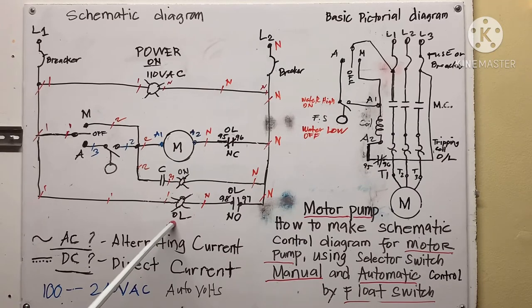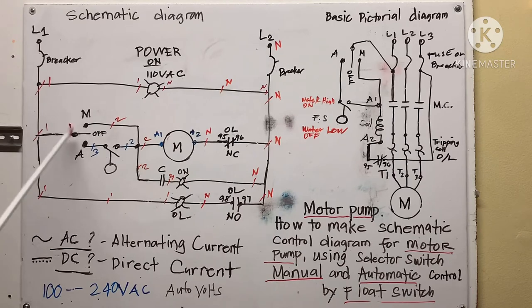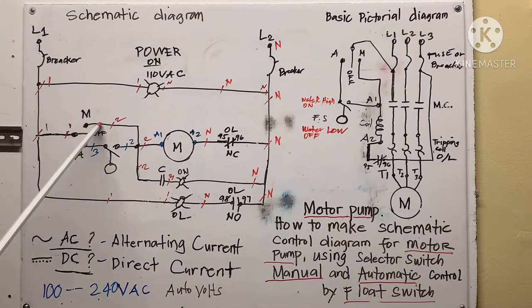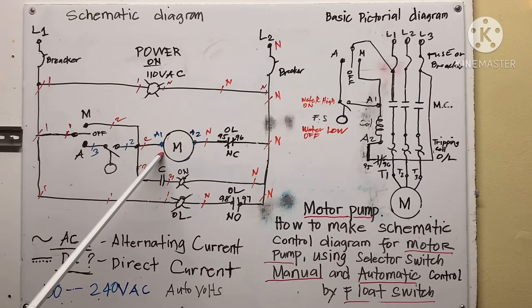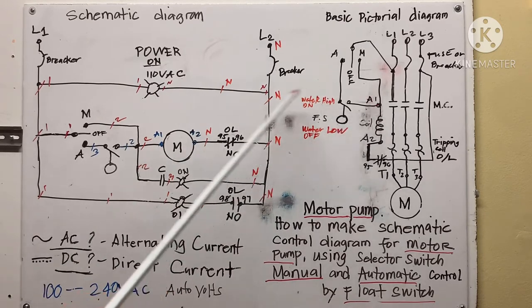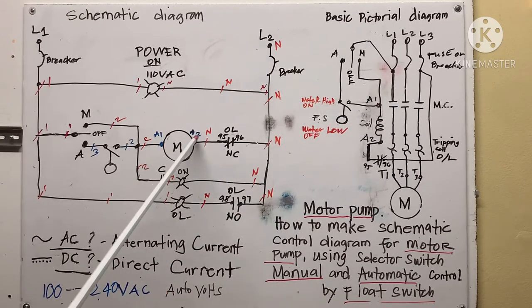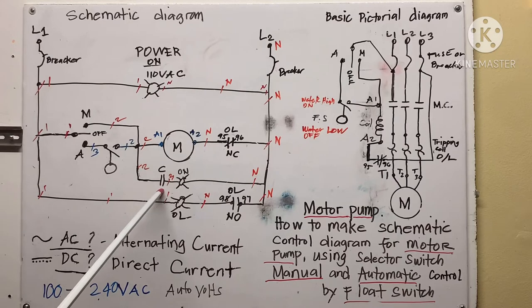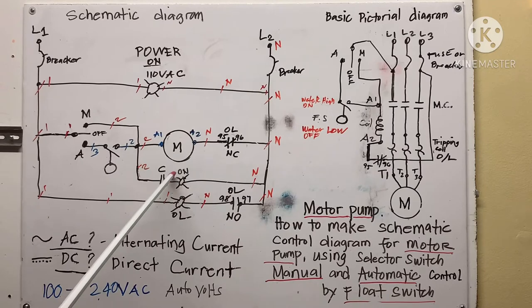This is the selector switch. When you put it in the middle it's off. When you turn to manual, the current goes to A1 — the circuit goes through there, so the motor is energized. The normally open contact for the contactor also energizes the additional indicator light.